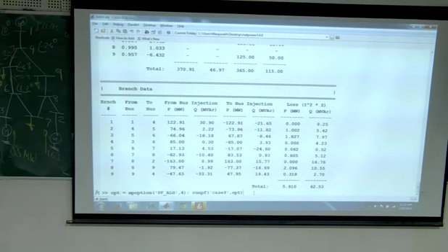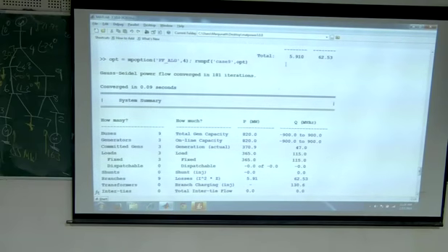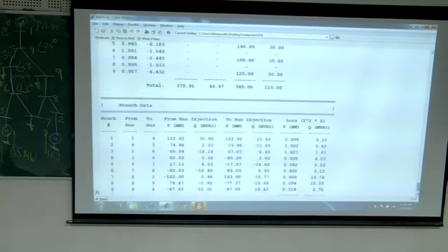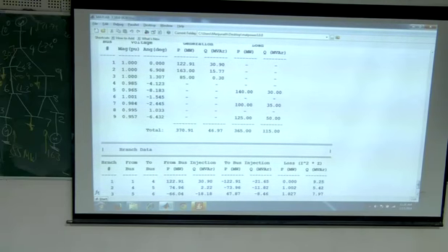Okay. So how much time did it take? I just ran it, and that's all, Gauss-Seidel method. But how many iterations did the Gauss-Seidel method take? We can check that. 181 iterations. So for the Gauss-Seidel method, we have done 1 iteration or 2 iterations, but for this 9-bus system it is taking that many iterations. And then more or less you got the same solution. Go down. So minus 8.18, whereas for Newton-Raphson it was very slightly different, minus 8.3. There are always slight differences in these methods.